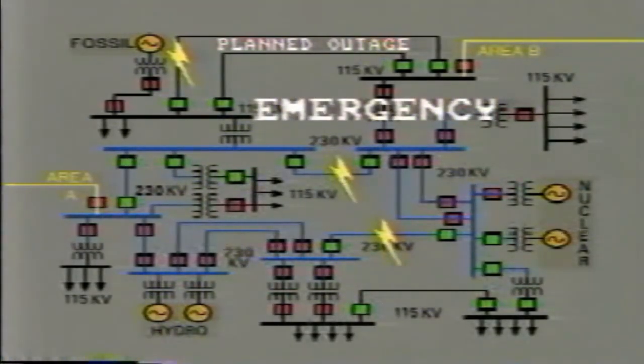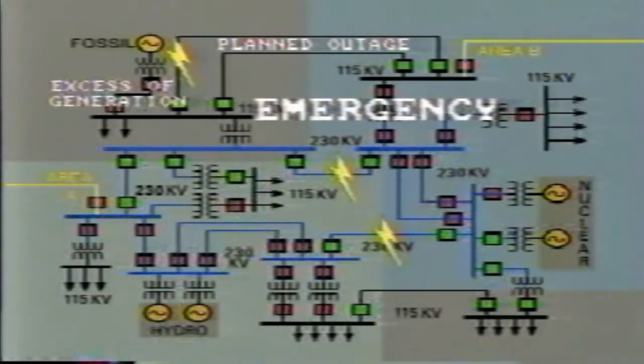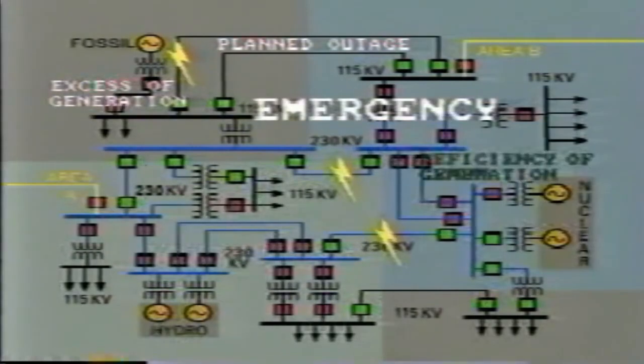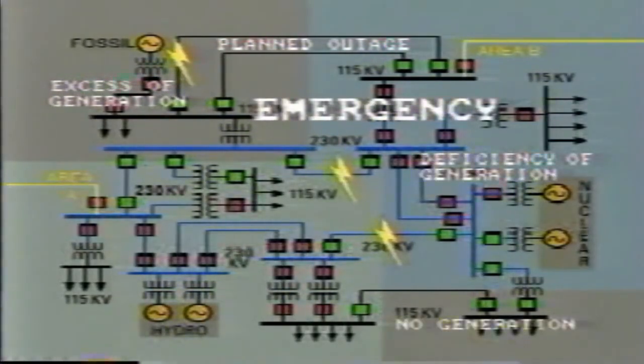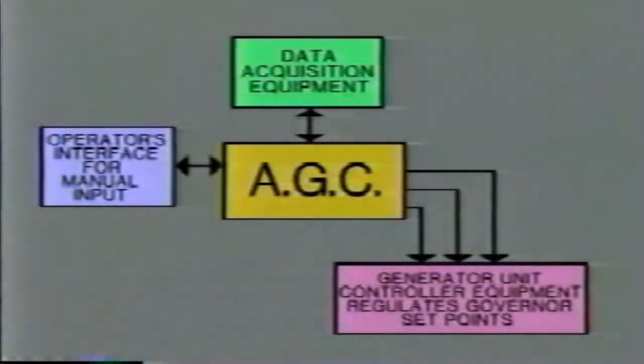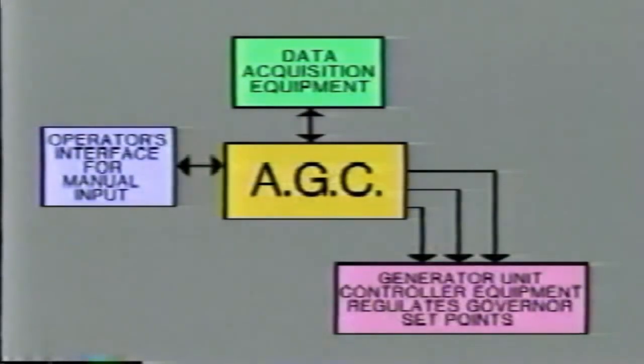The system would probably split into several disconnected islands, some with an excess of generation, some with a deficiency of generation, and perhaps other areas with no generation at all and hence a blackout. The AGC would have to be taken out of service. Otherwise, it may try to control generation in areas which are separated from its frequency measurement.